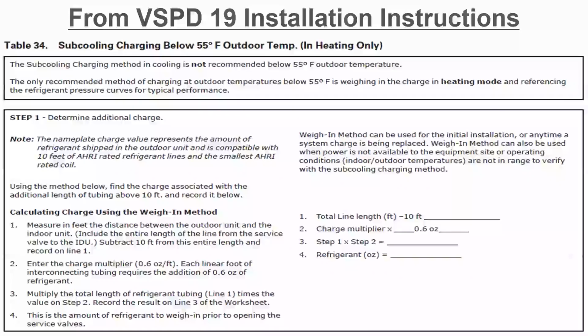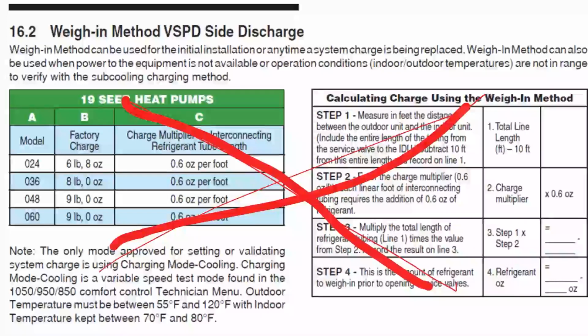I put this in here from the variable speed 19 installation instructions. Again, if you notate that in the installation manual, good for you. I used to write my numbers on the backside of the panel: my date of startup, my total line set length, and how much refrigerant I added. In the installation manual, it does have a 0.6 ounce per foot adder. We do not recommend this method.